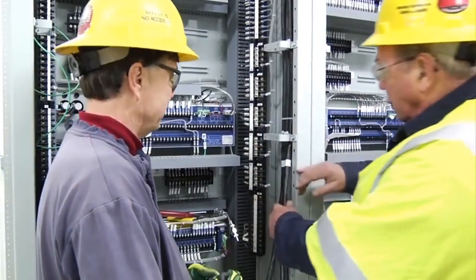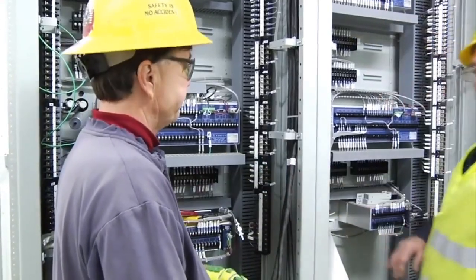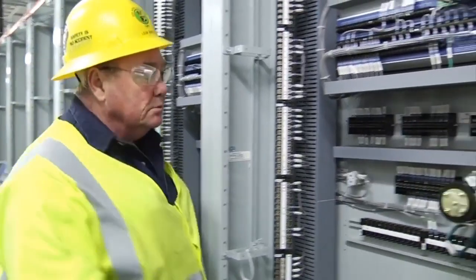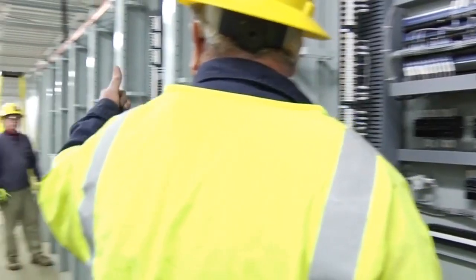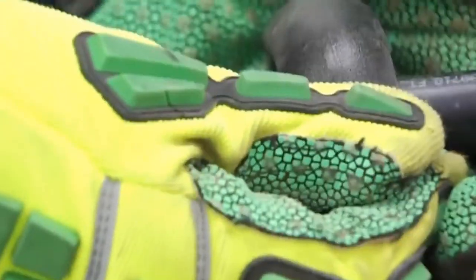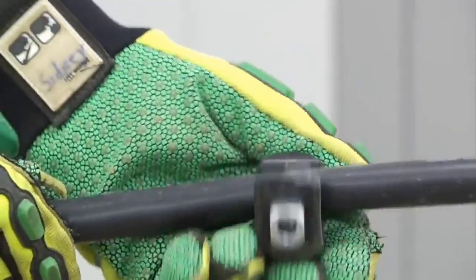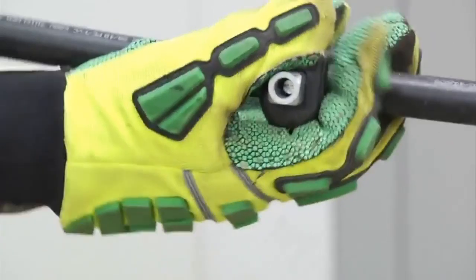For those working with control cables, contractor personnel shall have a second person verify that it is the proper cable and that it is de-energized. Only specifically designed wire skinning cutters shall be used. Pocket knives and/or razor knives like box cutters or carpet knives are not permitted for the purposes of wire skinning.